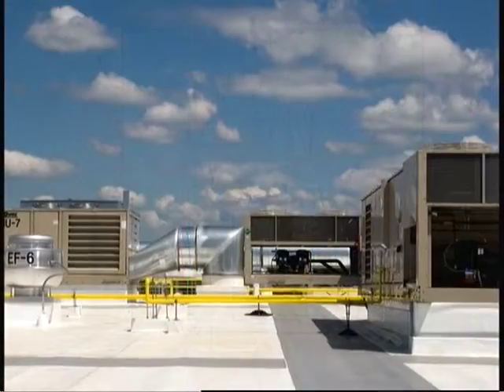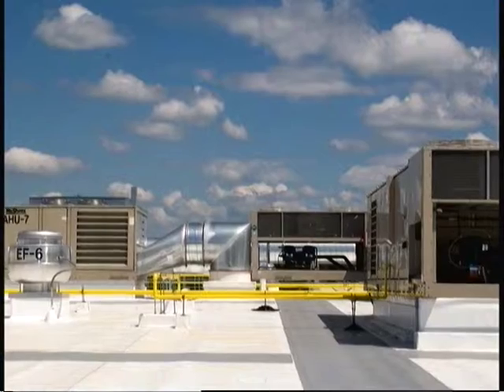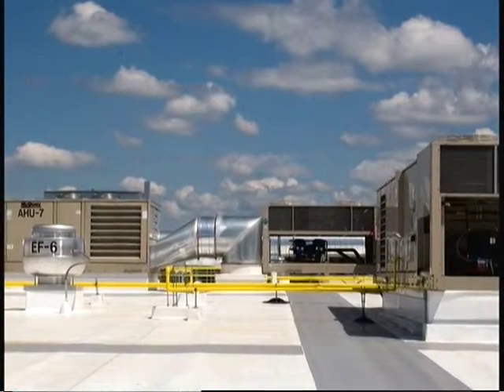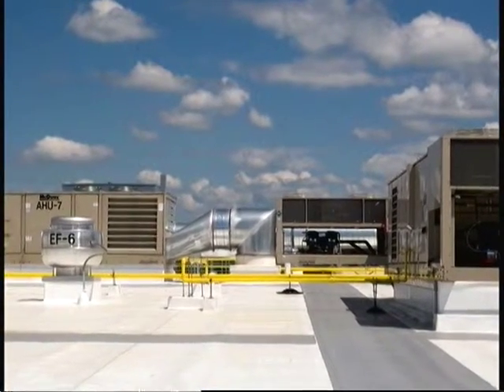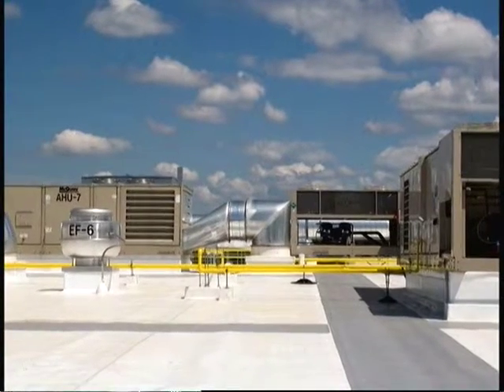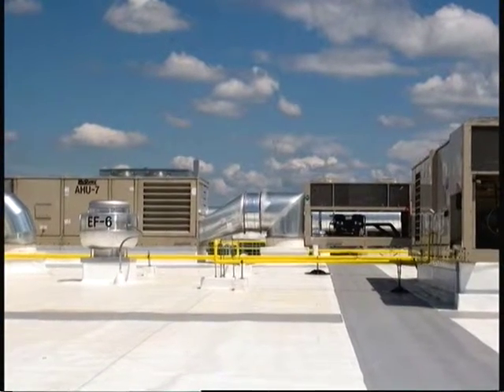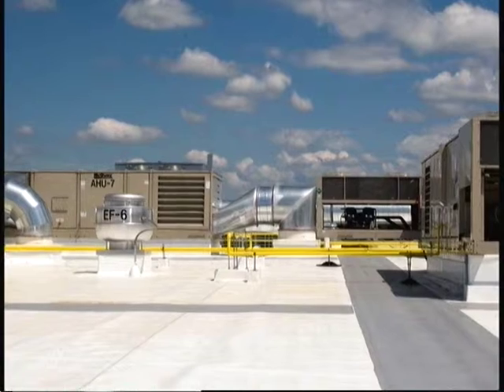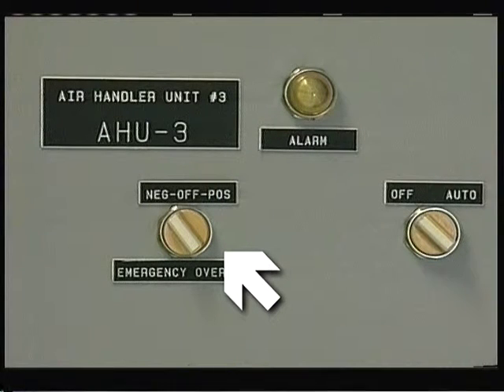Unit heating and cooling controls are enabled to supply 70° Fahrenheit discharge air within the limits of the heating and cooling equipment called for. Separate controls for the supply air fan and return air fan are provided so that the unit may be used to positively or negatively pressurize the space.